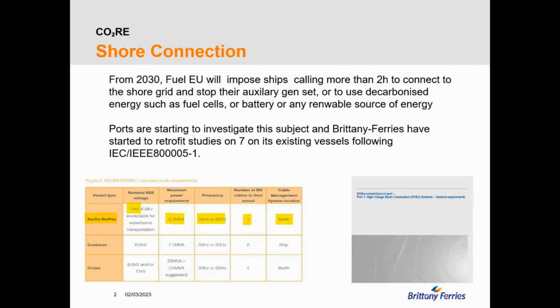This follows the norms developed for this, the IEC 80005 standard, which defines 3 different segments of ships that will have to connect to shore from 2030. One segment is ours, what we call RoPax or RoRo. The other two segments are container vessels or cruise vessels. For ferries, the requirement is to supply current at 11,000 volts or 6.6, with a power requirement of up to 6.5 MVA, which is quite a lot, and also have this current available in the two frequencies commonly applied on board ships, 50 or 60 hertz.